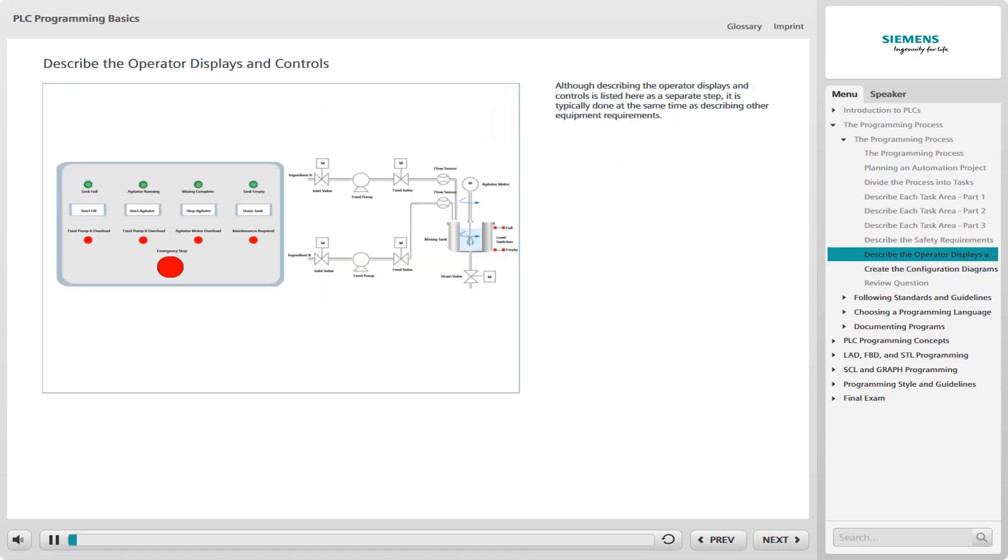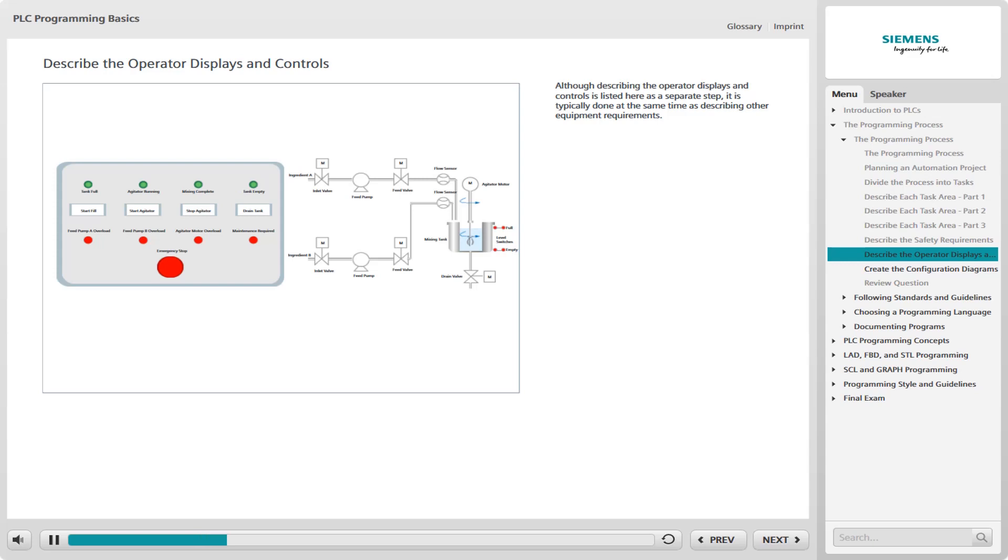While describing the operator displays and controls is listed here as a separate step, it is typically done at the same time as describing other equipment requirements. Some operator displays and controls may be associated with a panel on a machine or near some part of a process. These panels are typically wired to PLC inputs and outputs, and in some cases to safety devices as well.